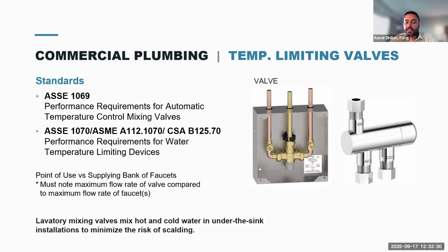Alternatively, the ASSE 1069 valve delivers up to 120-degree tempered water to serve showers in places such as prisons, schools, health clubs, and similar shower rooms that utilize a push-button metering system in a single temperature shower system.